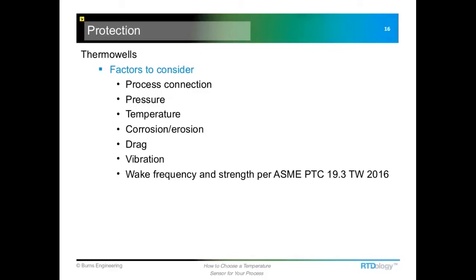And then of course the pressure and temperature. Typically, temperature is not too much of a concern for a thermowell where an RTD is being used, because RTDs will go up to about 500 degrees C, which is a typical industrial grade temperature limit for an RTD, and usually any of the stainless steels or even carbon steel is just fine at those temperatures.